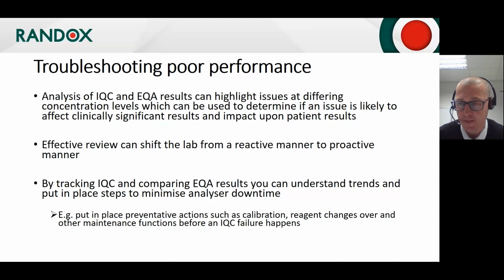So for example, I will review my QC and I will start looking at where I'm going to be getting trending rules. So if I've got 10x breaches or 7T breaches, if they're moving away from the mean in a positive or negative manner, but they're starting to pass through 1 SD and 1.5 SD, 2 SD, 2.5 SD, it's not going to be long before they're breaching 3 SD, and at that point, I'm going to have to stop running that test.